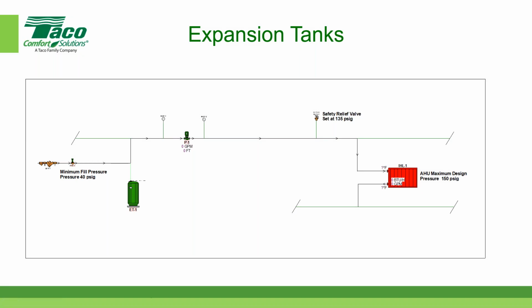Well, for those of you that are familiar with relief valves, they're a very simple device. It's a valve with a disc inside held closed with a spring. The spring is calibrated. Usually there's a knob at the top you can open and close to set the relief valve pressure. But if it gets to the setting of 135, they can leak or drip or weep. Sometimes we use the word weep. Well, we don't want it to weep.